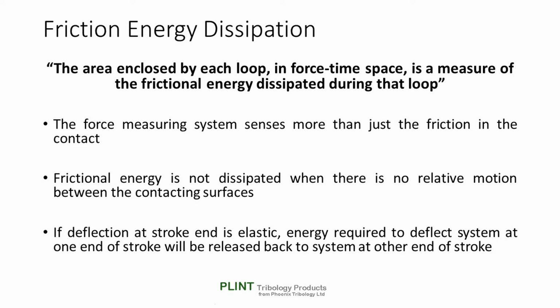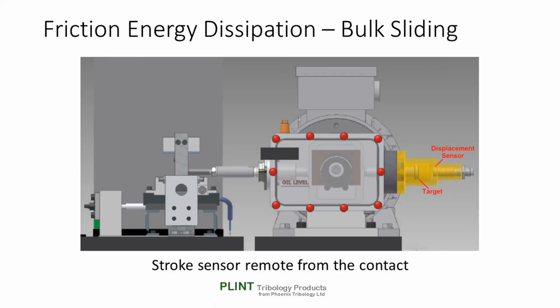Assuming the deflection at stroke end is elastic, then the energy required to deflect the system at one end of the stroke will be released back to the system at the other end of the stroke. In this case, the area enclosed by the loop is not a measure of the energy dissipated in the system. The first thing to consider is where the displacement is being measured.